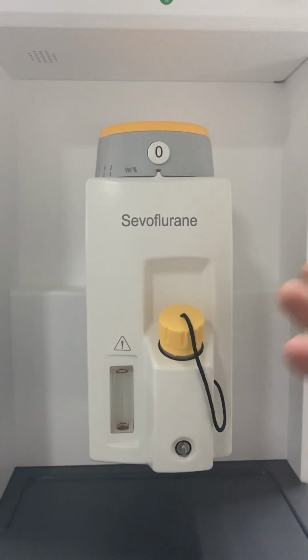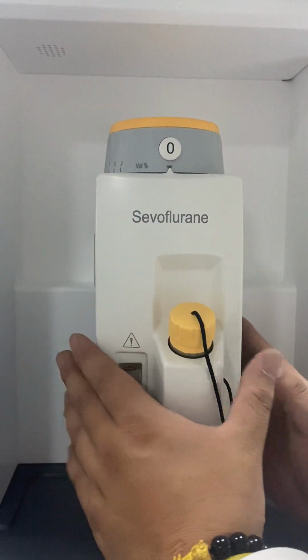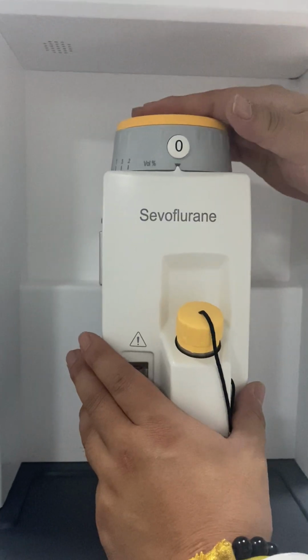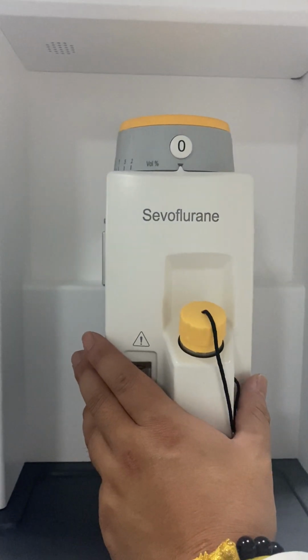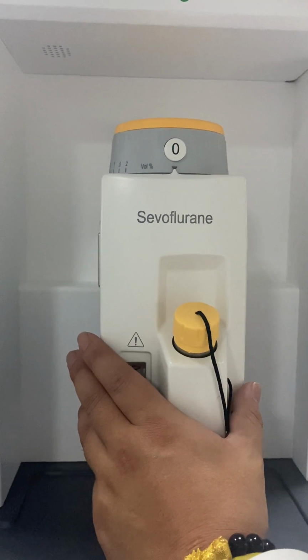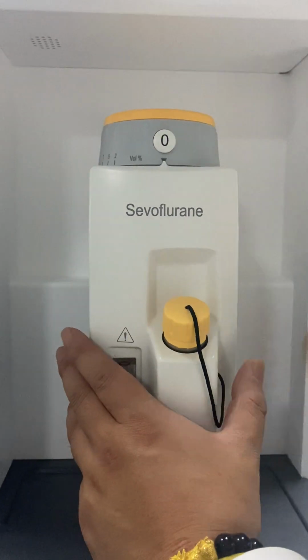And also it has the interlock function. If you are putting 2 vaporizers together here, then if you open one of the vaporizers, the other one will always be closed. So you can only use one vaporizer at one time.